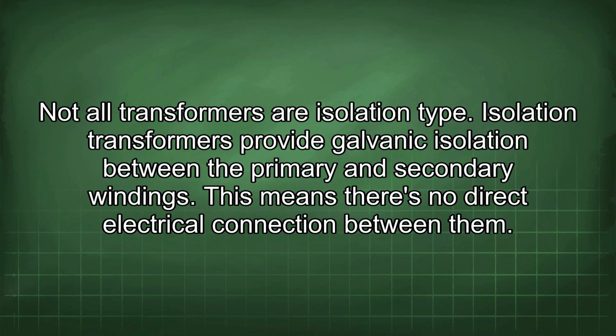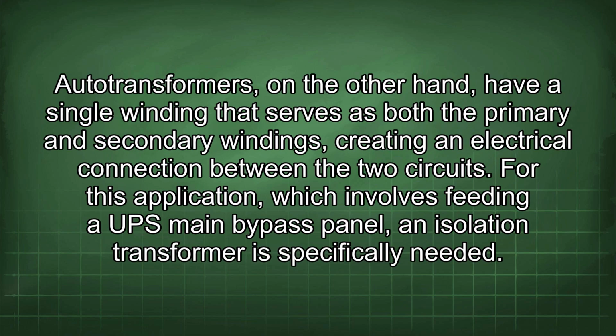Not all transformers are isolation type. Isolation transformers provide galvanic isolation between the primary and secondary windings. This means there's no direct electrical connection between them. Autotransformers, on the other hand, have a single winding that serves as both the primary and secondary windings, creating an electrical connection between the two circuits.